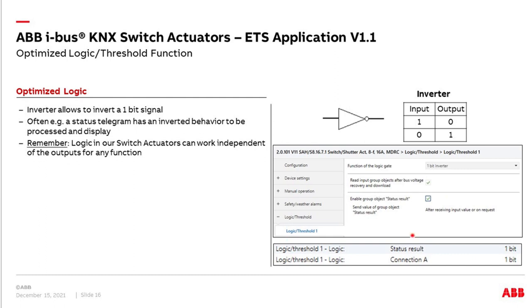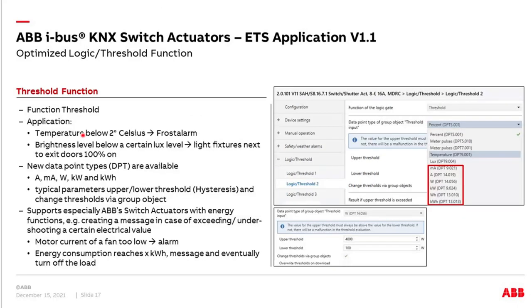Parameterization is very simple. Of course the results have to be enabled, and you have two group objects: connection is the input, and results is the output. So we added the inverter. Regarding the threshold function — what is threshold function? Also very important to compare values. For example, if the temperature is two degrees outside you would like to trigger something. This was existing already. What did we do? We added further data types, especially needed in our Switch Actuators with energy functions: milliampere, ampere, watt, kilowatt, watt-hour, and kilowatt-hour. This data we can now also process in the threshold to compare something.